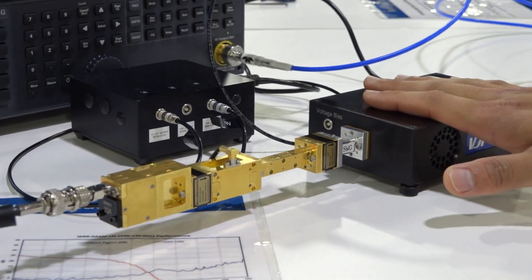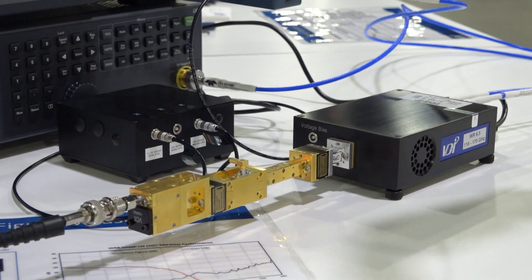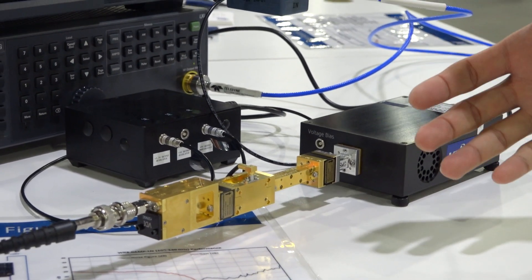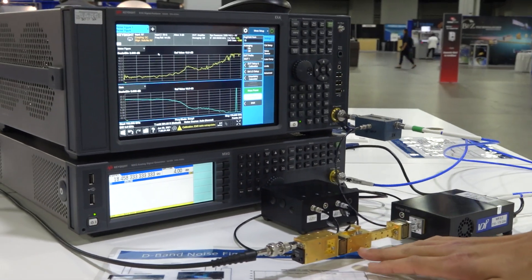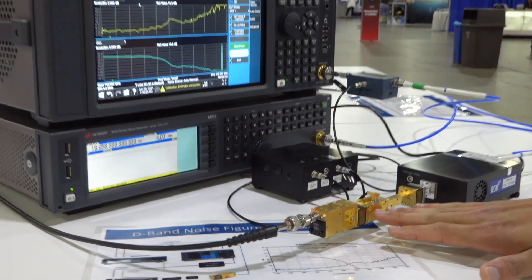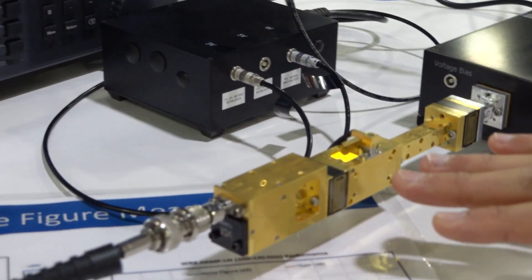We run an onboard calibration, and then once the calibration is finished, we place the DUT, which in this case is an LNA low noise amplifier operating around 90 to 140 gigahertz.